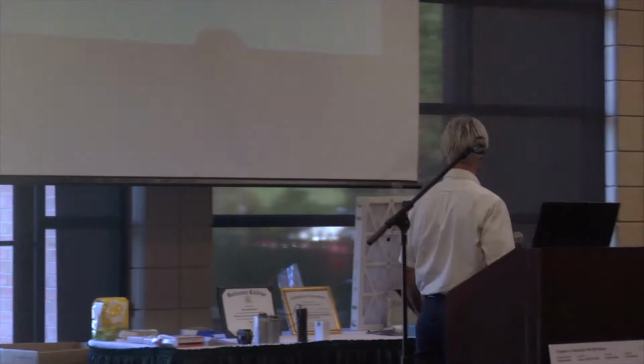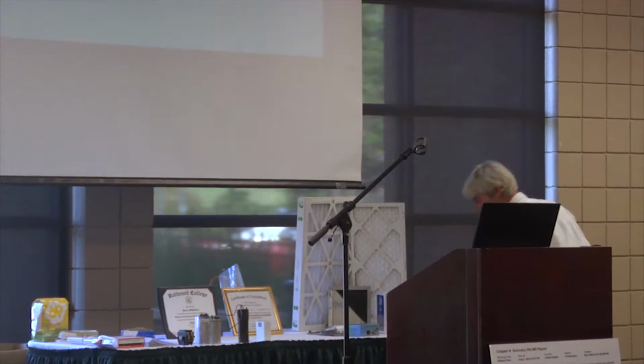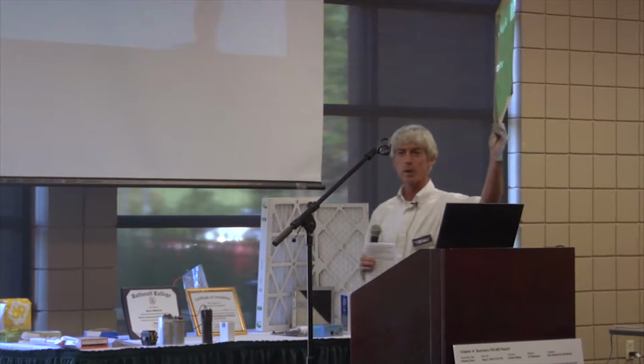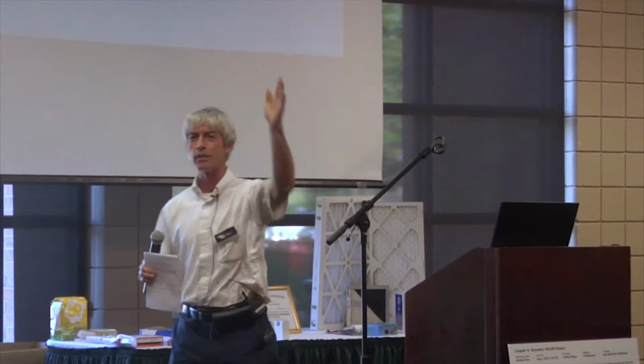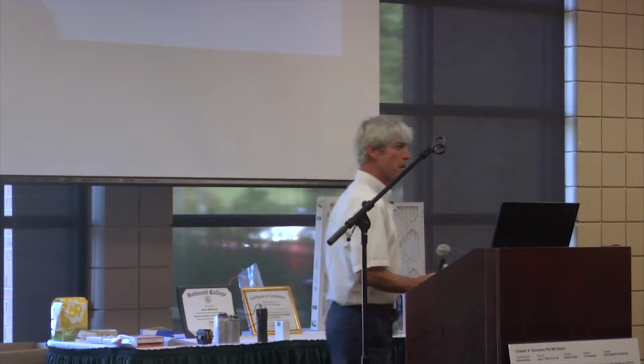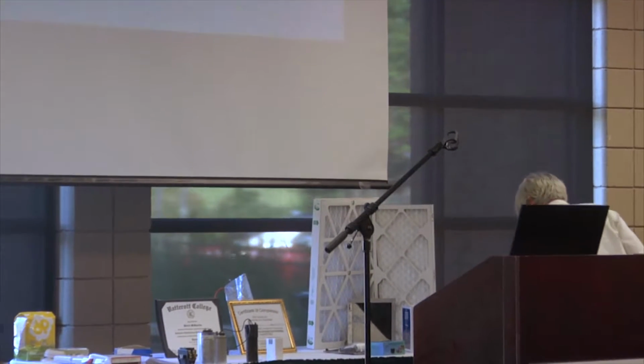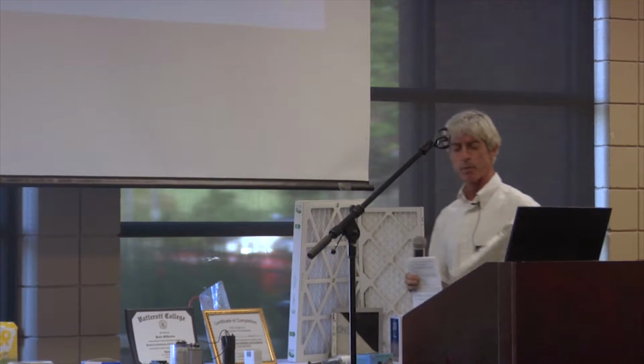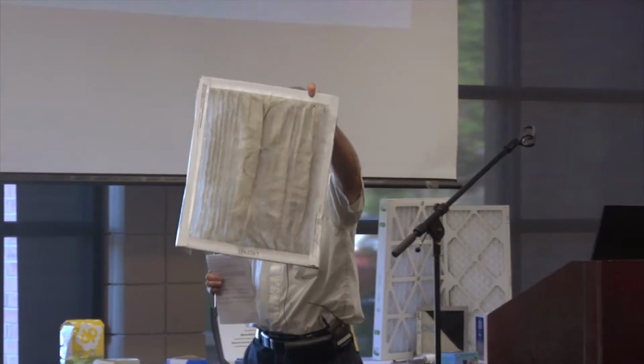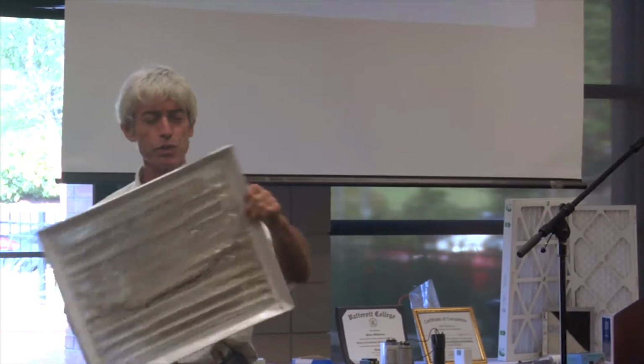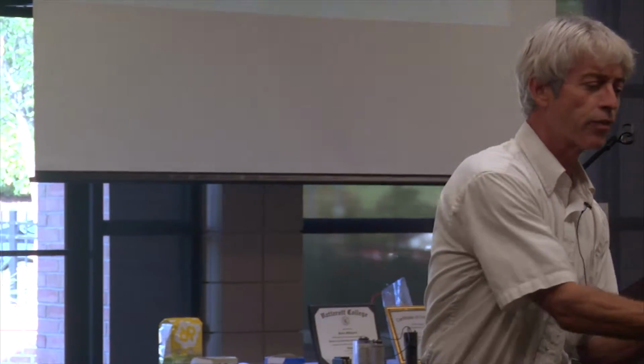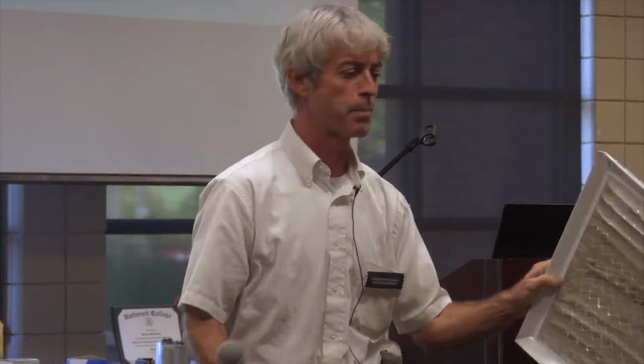With filters, they come in many different types. Most of us have seen this one right here. What I want you to do with this one is throw it out. Why even bother? The other filters could be right but installed wrong. Filters are designed with the metal side facing the equipment. As the air flows through, it keeps the filter intact. This one was installed backwards, so the filter is being pulled apart.